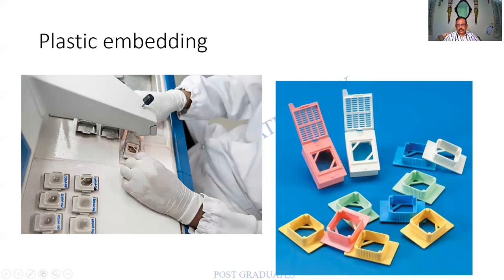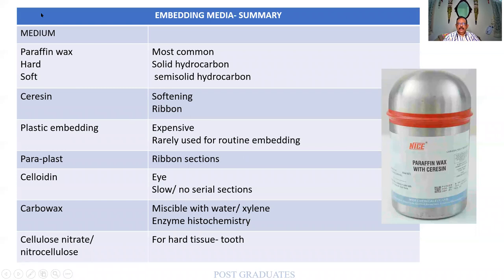On tissue block holders, sometimes circular or rectangular rings are used for embedding and section cutting. The embedding machine receives wax from above, the tissue is embedded, and placed on a cold plate to solidify. Regarding the different embedding media — to summarize: celloidin is used for the eye, paraplast for ribbon sections, plastic embedding is expensive, ceresin is used for softening paraffin and for cutting ribbon sections, and nitrocellulose is for hard tissues such as a tooth. Always order paraffin with ceresin; check the melting point.